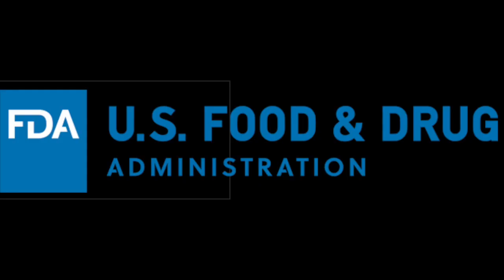And so with that, let's dive into the paper. And one of the things that they talk about in the paper very explicitly is that there are no published FDA, Federal Drug Administration, which is the agency in the US that approves or clears medical devices and drugs. There are no published FDA standards for either testing or validating or approving cuffless blood pressure devices. And that is quite correct. They also talk in the paper about two standards by standards organizations. One is the ISO 81060. The other one is IEEE 1708, which talk about testing of blood pressure devices. Neither standard, of course, is an FDA standard. Neither standard is binding on the FDA. And so there is some uncertainty there.